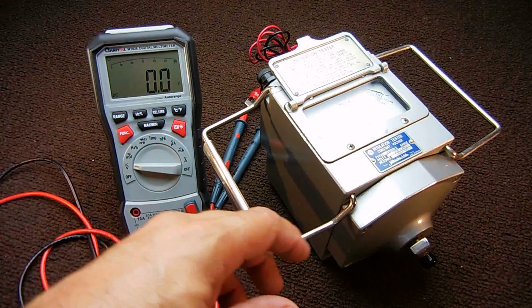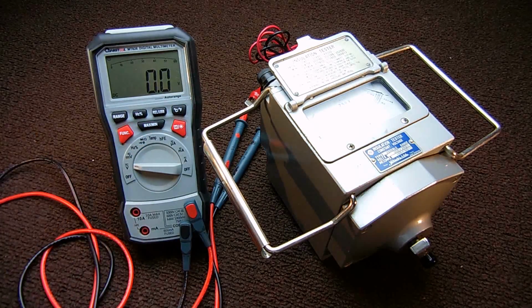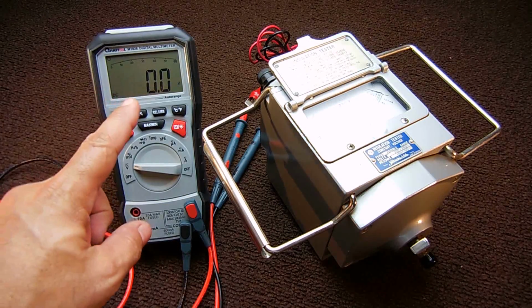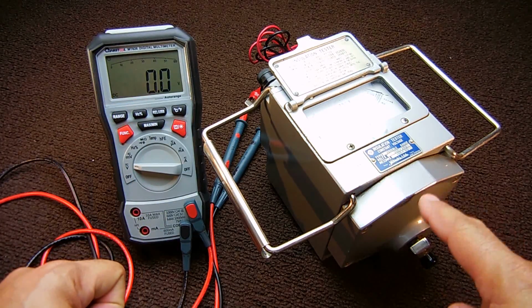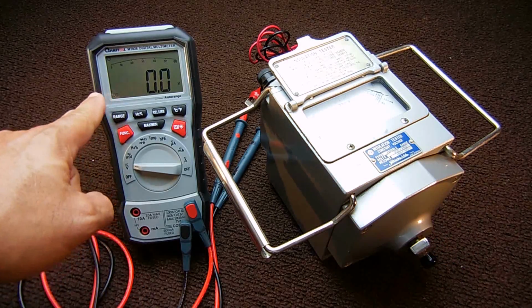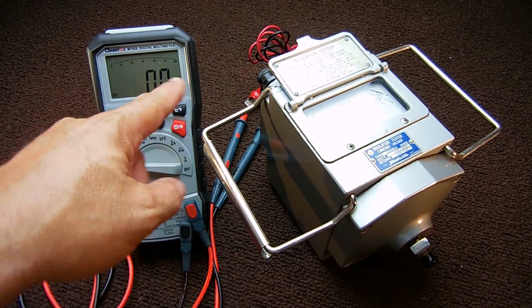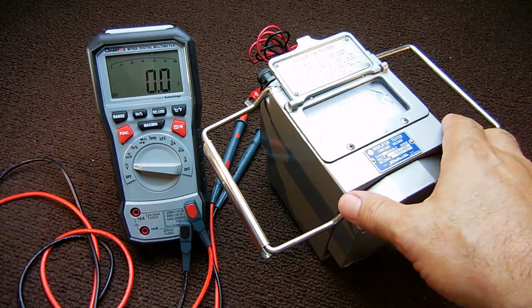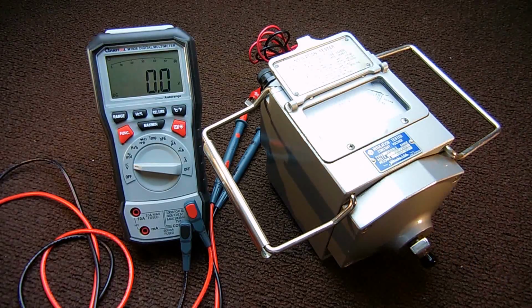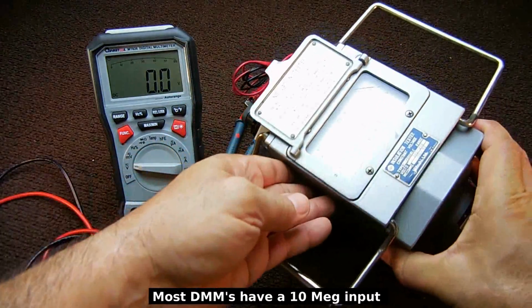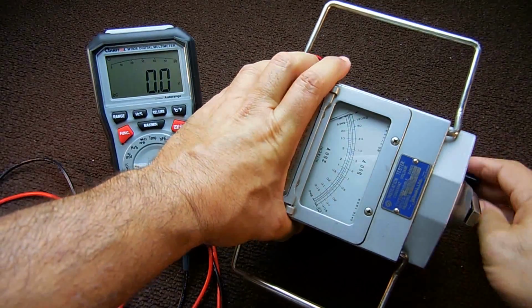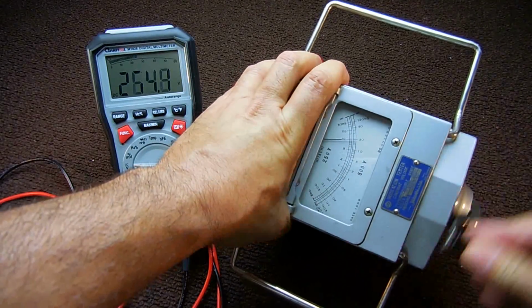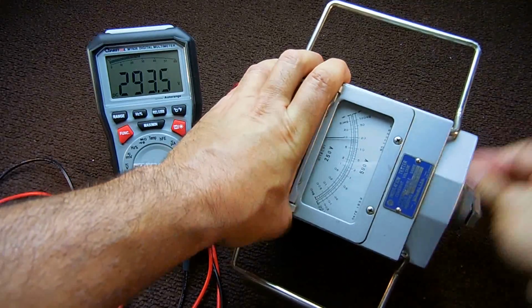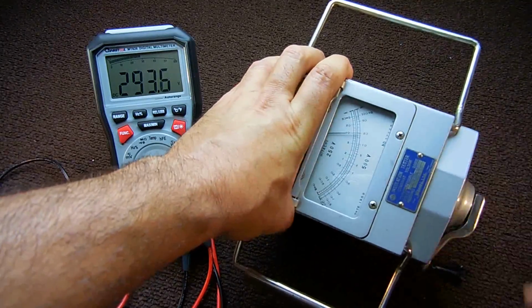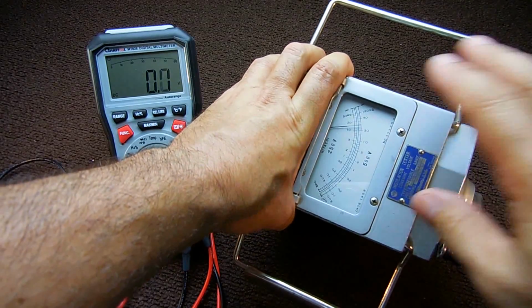What I did now is I connected up the output of the Megger to my digital meter on a DC voltage range. It's set for 250 volts. This is a 10 megohm input, so when I crank this up to a high speed, you're going to see the output voltage displayed right here, and right on the 250 volt scale, I'll tilt it, it's going to go right to 10 megohm. Here we go. See, it went right up to the 10. So this is very accurate.